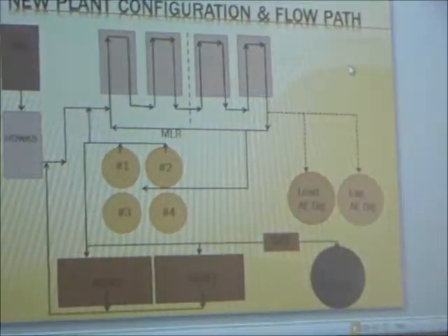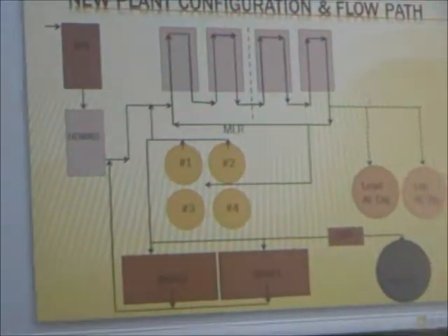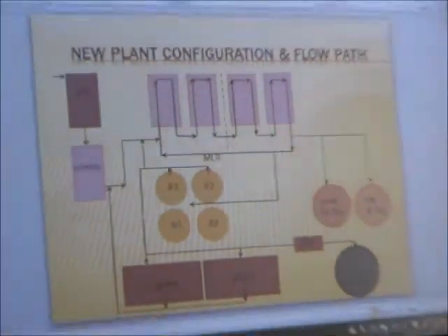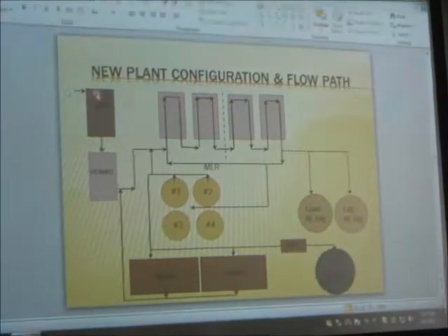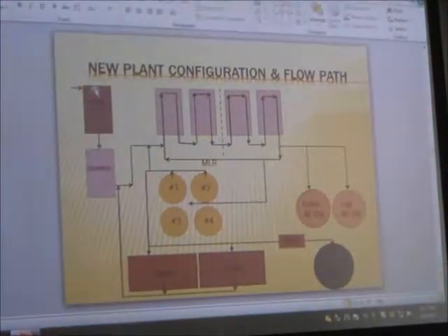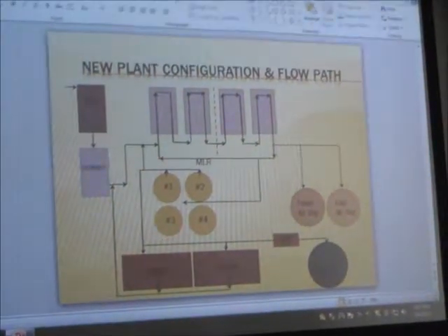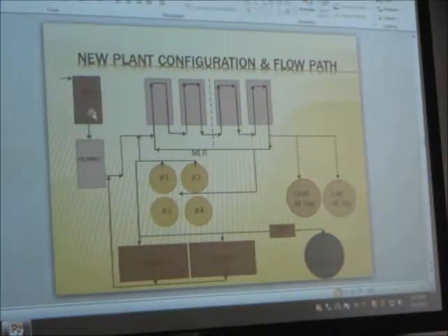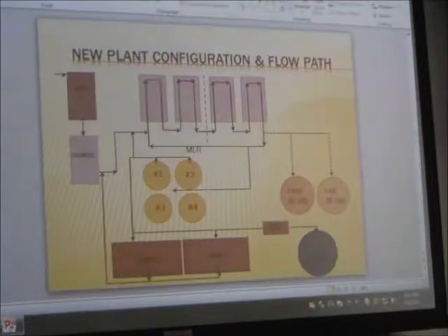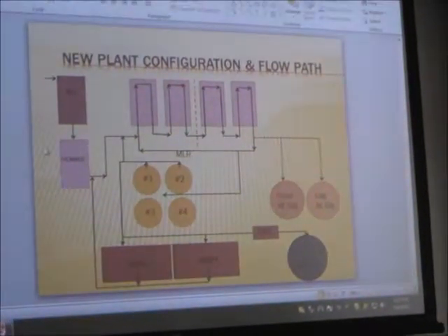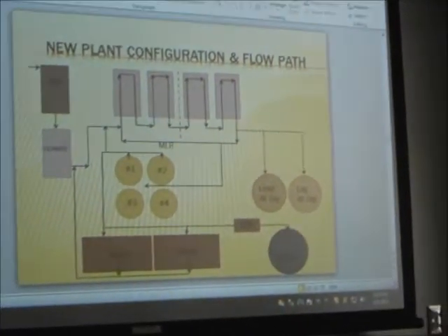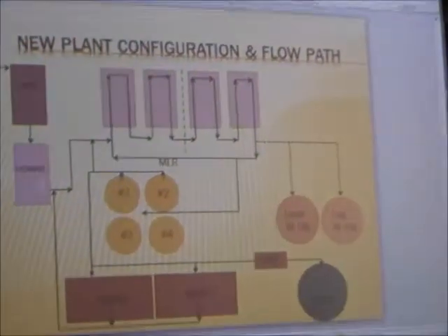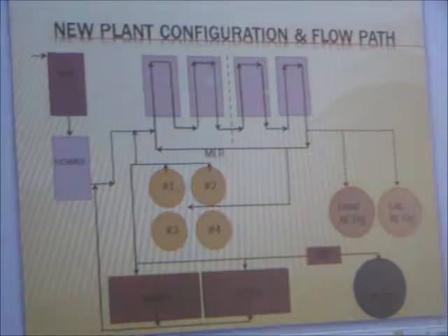This is a quick basic schematic. Again, you've seen it in real life. IPS is here. This is where the collection system comes to a point, and into a large deep wet well. It's pumped up to the headworks, gets its screening, automatic bar screens, and grit removal, and then gravity flows into your aeration system.